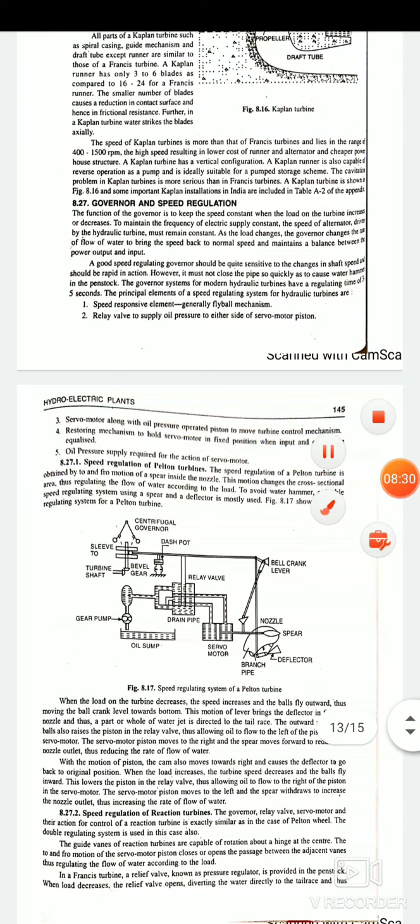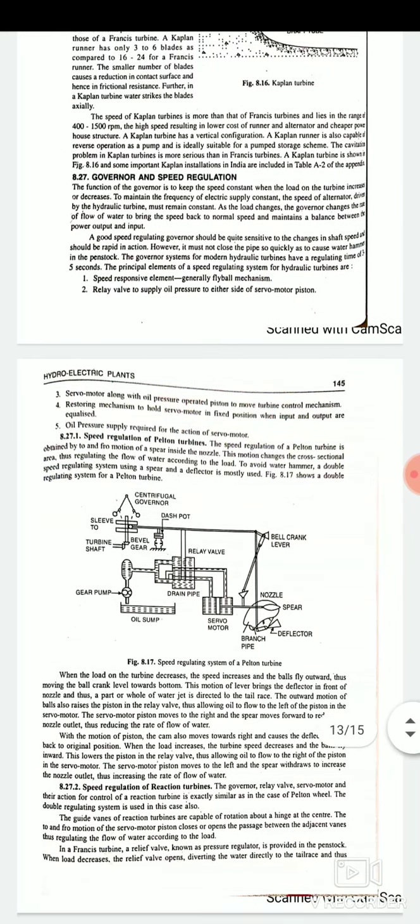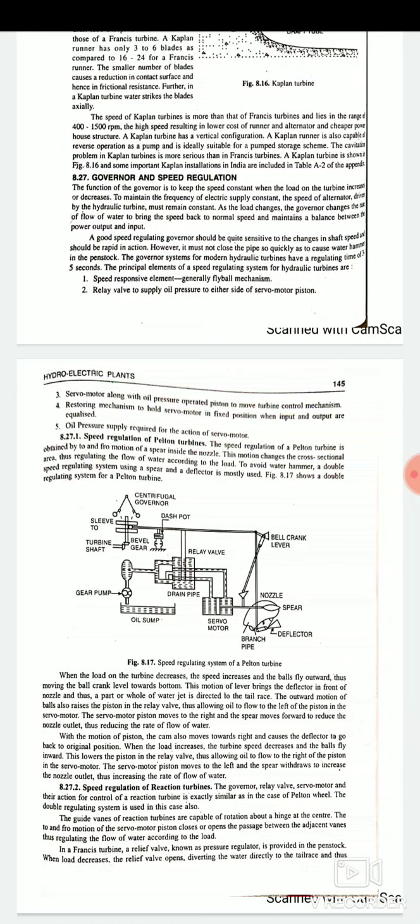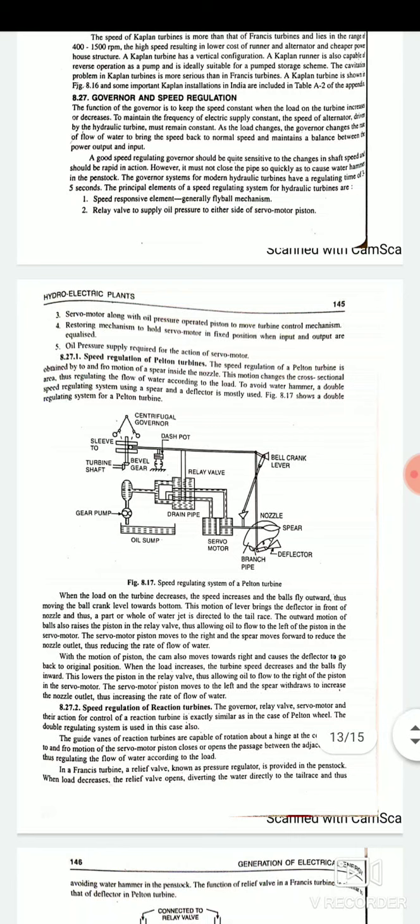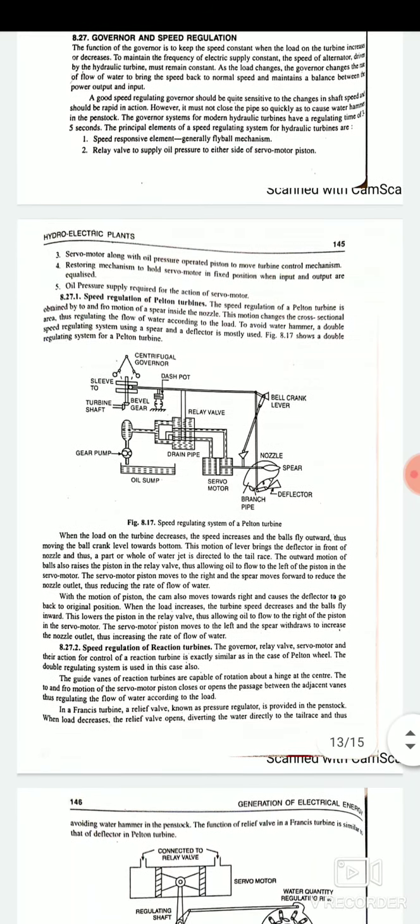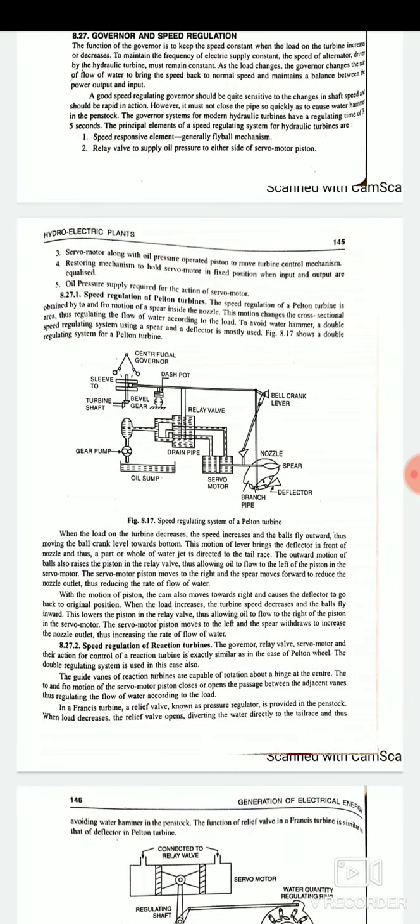Next is your governor and speed regulation. The function of the governor is to keep the speed constant when the load on the turbine increases or decreases. To maintain the frequency of electric supply constant, the speed of the alternators driven by the hydraulic turbines must remain constant. As the load changes, the governor changes the rate of flow of water to bring the speed back to normal speed and maintains a balance between the power output and input. A good speed regulating governor should be quite sensitive to the changes in the shaft speed and should be rapid in action. The principal elements of a speed regulating system for hydraulic turbines are: speed responsive element, generally flyball mechanism; relay valve to supply oil pressure to either side of servo motor piston; servo motor along with oil pressure operated piston to move turbines control mechanisms; fourth one is restoring mechanism to hold servo motor in fixed position when input and output are equalized; and the last is oil pressure supply required for the action of servo motor. So these are the principal elements of a speed regulating system for hydraulic turbines.